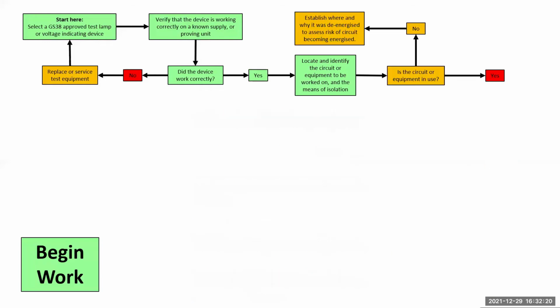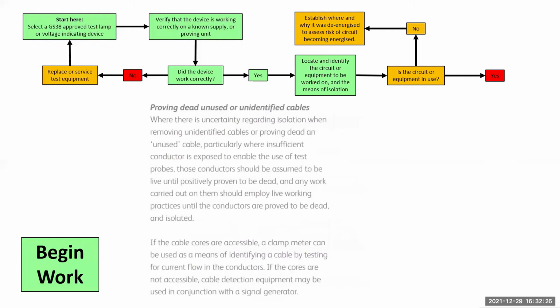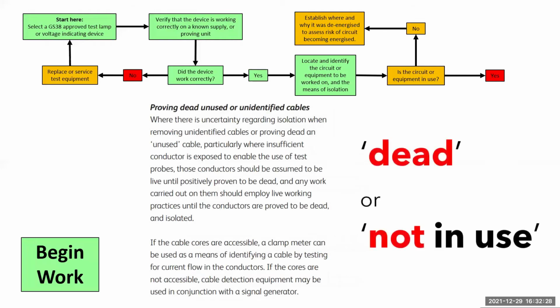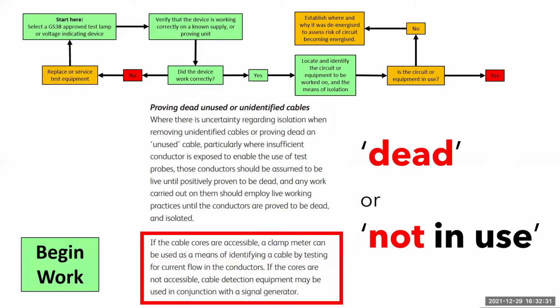If you come across an unknown circuit, you must assume that the cable is live until proven otherwise, even if it is marked up as dead or not in use. The Best Practice Guide 2 suggests that a clamp meter can be a means of identifying a cable, but that will only work if current is flowing, so it suggests using cable detection equipment with a signal generator.